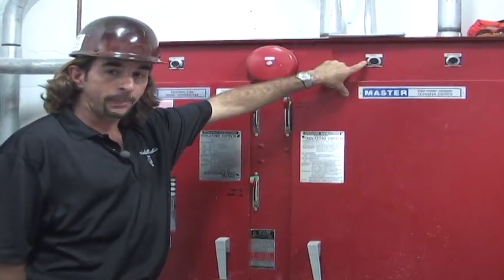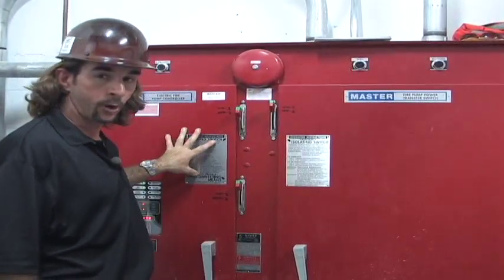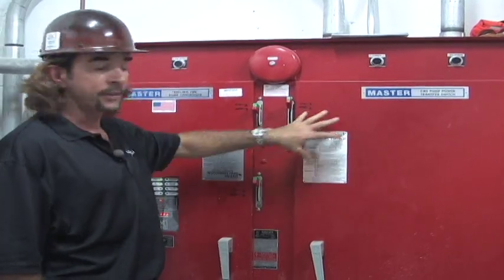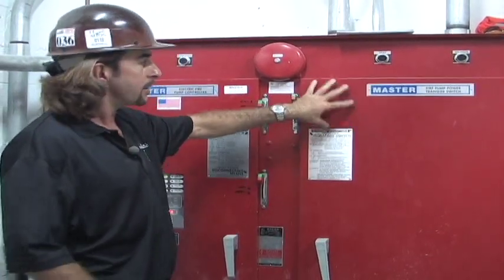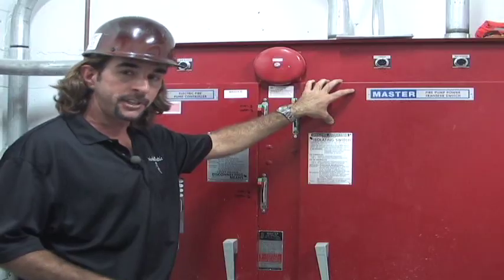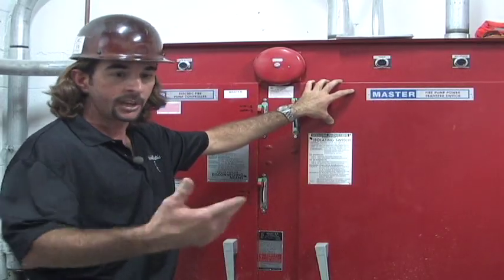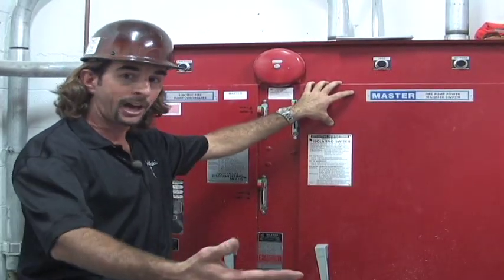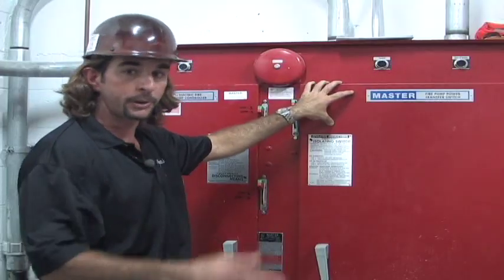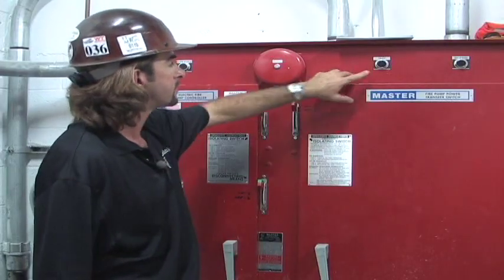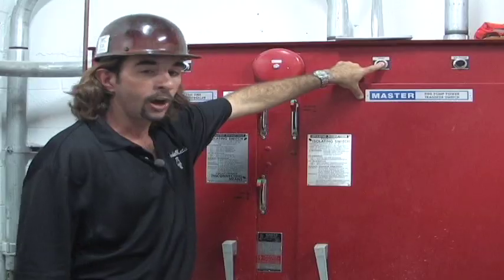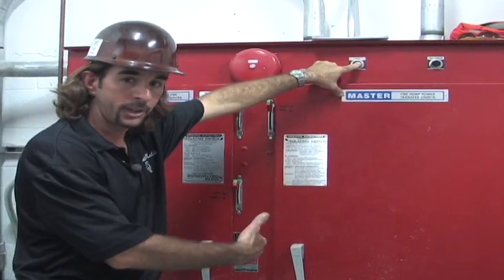We're going to push the test button, which is going to transfer from normal power over to the emergency generator. This usually takes anywhere from 10 to 15 seconds to make the change. And then the fire pump should start right back up because we are on a low pressure. We are flowing water right now. You need to continue to hold the button until it completely makes the transfer.